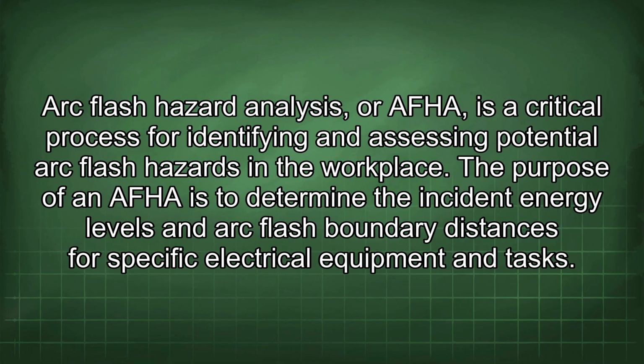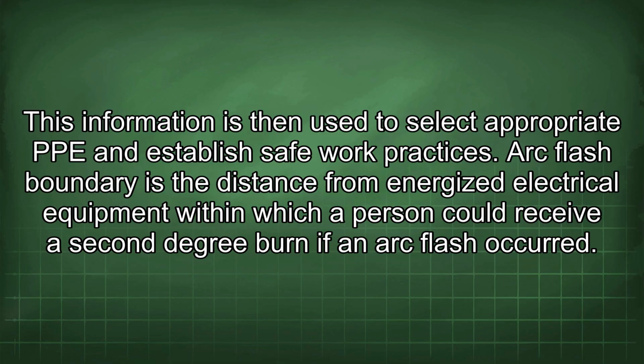Arc flash hazard analysis, or AFHA, is a critical process for identifying and assessing potential arc flash hazards in the workplace. The purpose of an AFHA is to determine the incident energy levels and arc flash boundary distances for specific electrical equipment and tasks. This information is then used to select appropriate PPE and establish safe work practices.